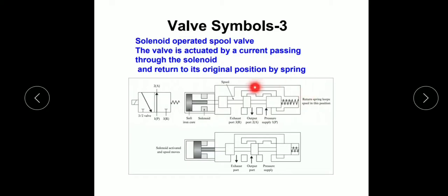And this shows the working of a solenoid valve, and here there are 2 solenoids with soft iron core. When this is attached to the solenoid valve, this central valve will move towards the right side, and the spring gets compressed and there will be a flow through this side. And when the current is dismissed or solenoid is released, the valve will come back to initial position and the flow will be in this side. This is the working of a solenoid valve with spring return.